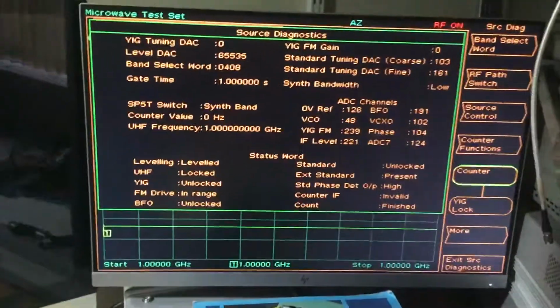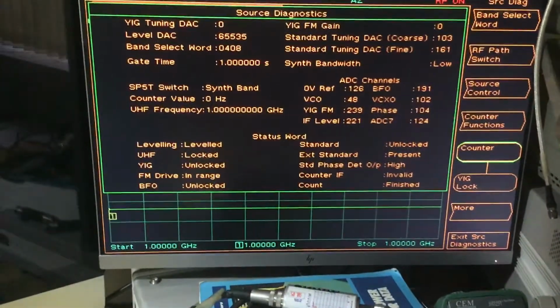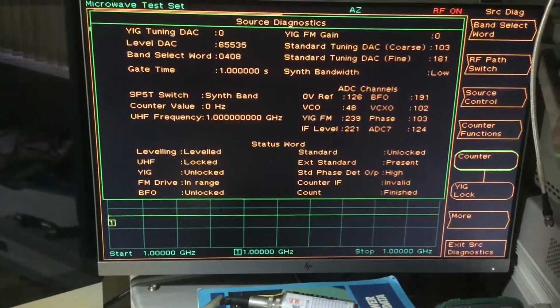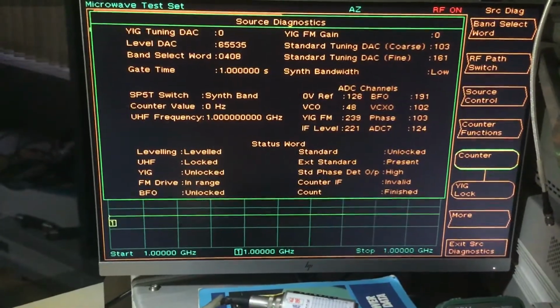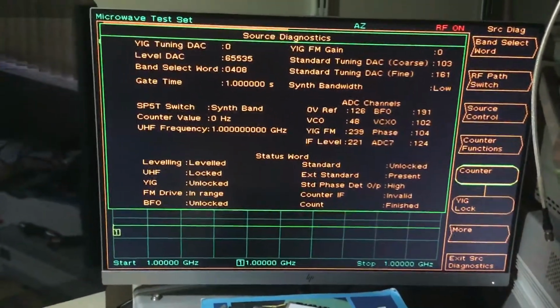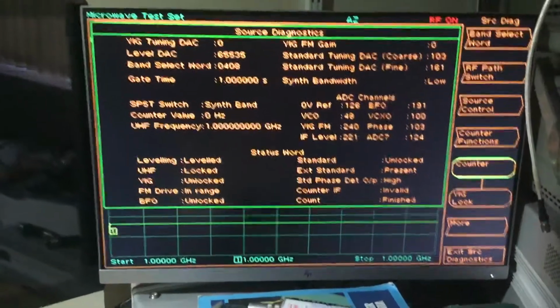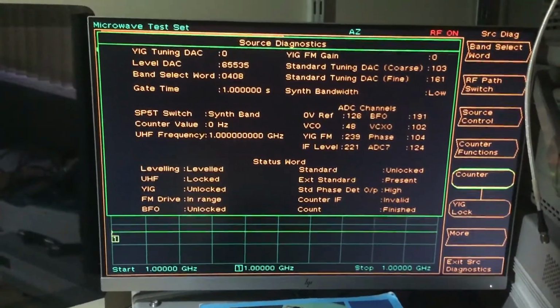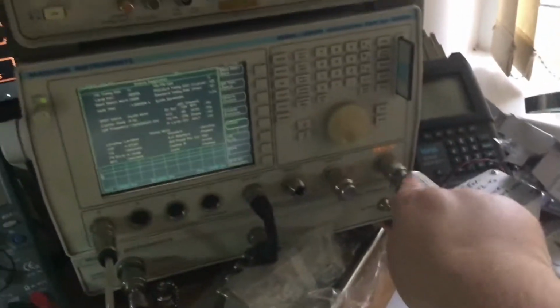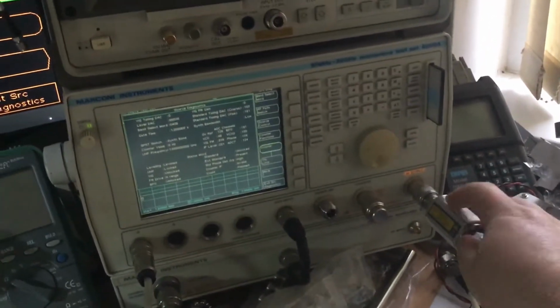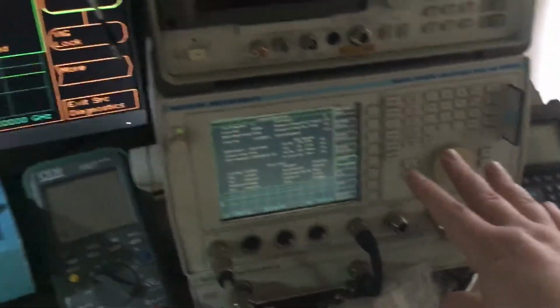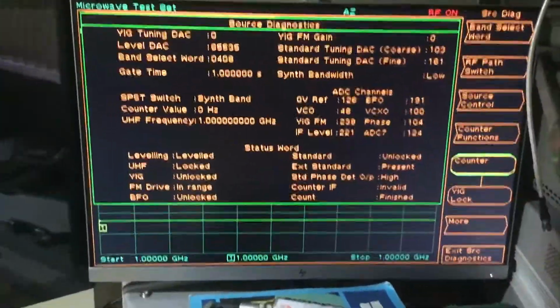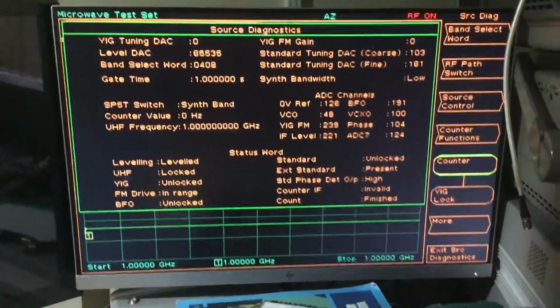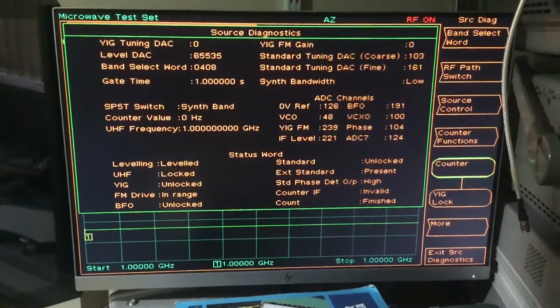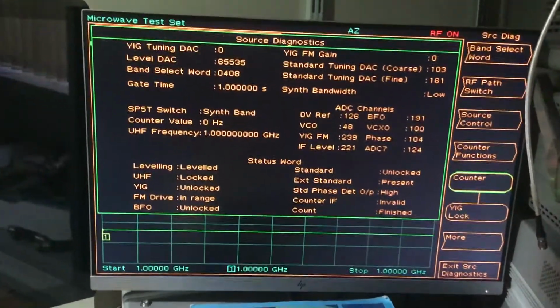It's quite a lengthy process. If you're doing it broadband, it can take hours even, because you have to input the linearity data and all the calibration data into the instrument for the sensor, as they've all got their own linearity data printed on them. You input all that first, calibrate the sensor, go to your calibrations menu, which is password protected by Marconi, and start the broadband power measurement, which will run from 10 megahertz to 20 gigahertz.